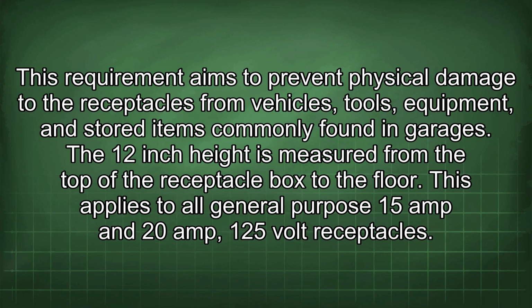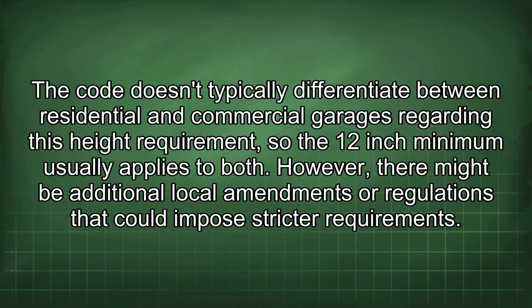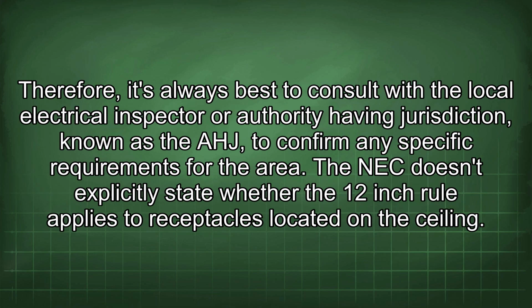This applies to all general-purpose 15-amp and 20-amp, 125-volt receptacles. The code doesn't typically differentiate between residential and commercial garages regarding this height requirement, so the 12-inch minimum usually applies to both. However, there might be additional local amendments or regulations that could impose stricter requirements. Therefore, it's always best to consult with a local electrical inspector or authority having jurisdiction, known as the AHJ, to confirm any specific requirements for the area.